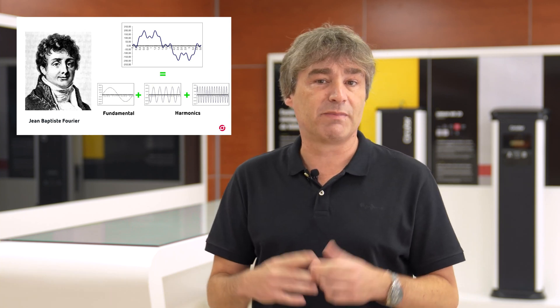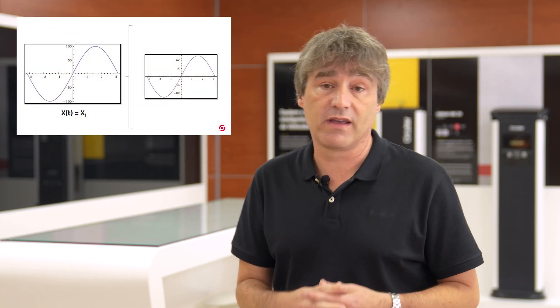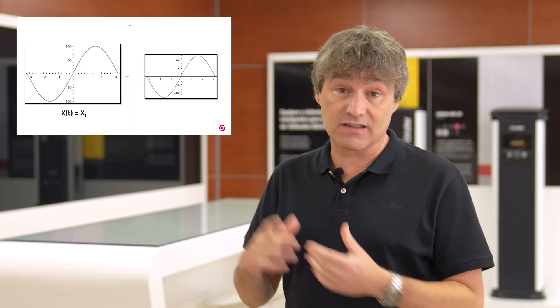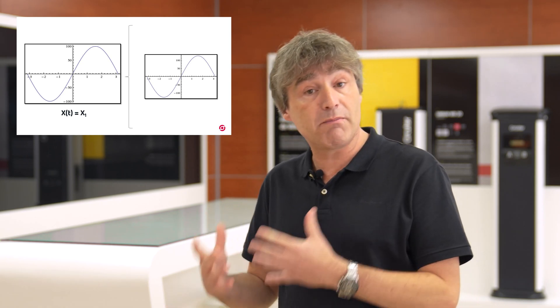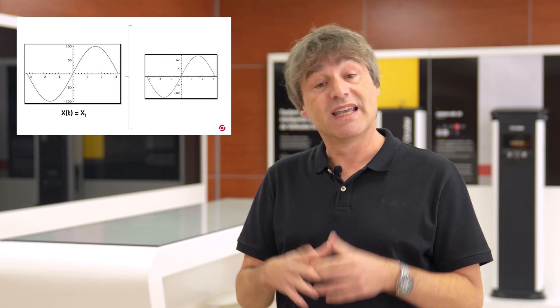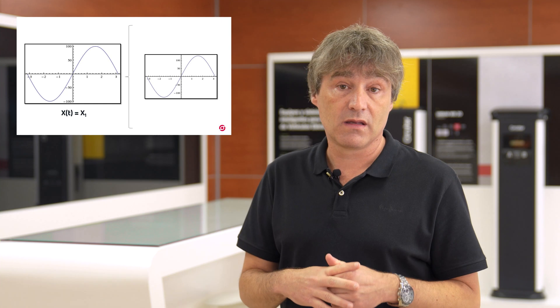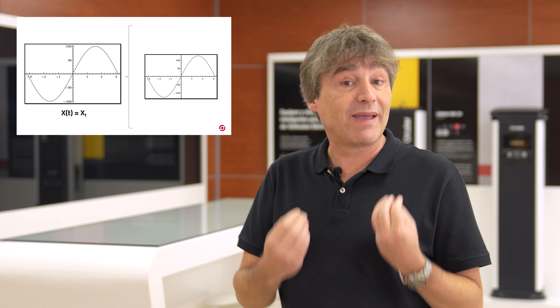This definition probably sounds a little bit tricky, but with the following example, for sure it would be much easier to understand. Let's assume that the wave on the screen stands for the current wave in a 50 Hz network. This means that this wave happens 50 times in one second, so it has a time period of 20 ms. In a 60 Hz network, the time period would be 16.6 ms. This is what we call the fundamental wave.